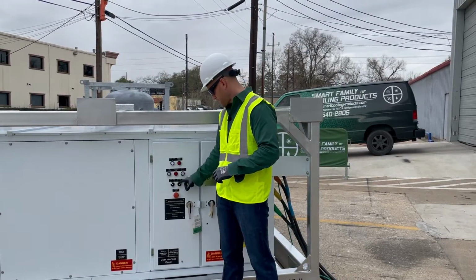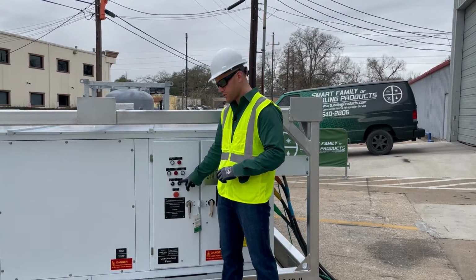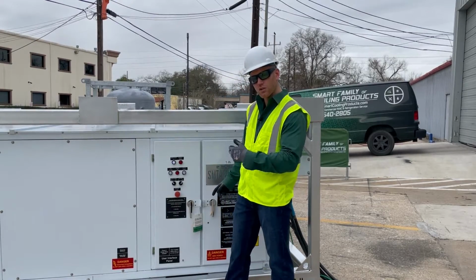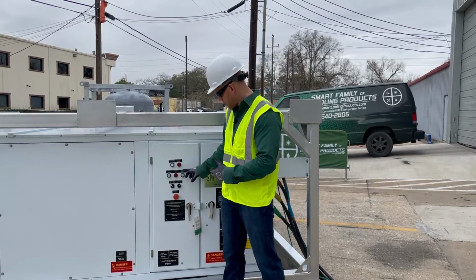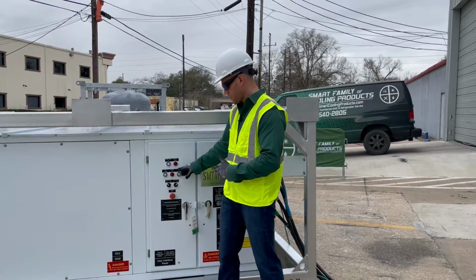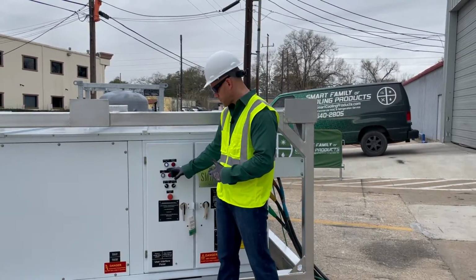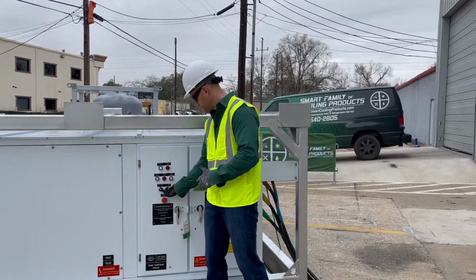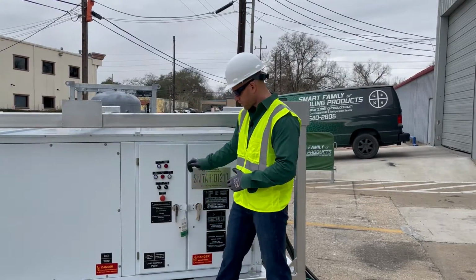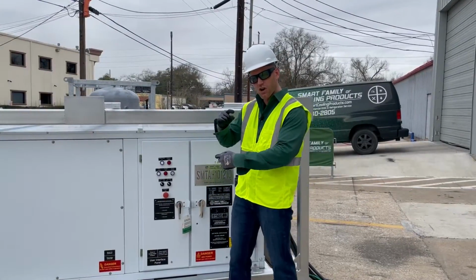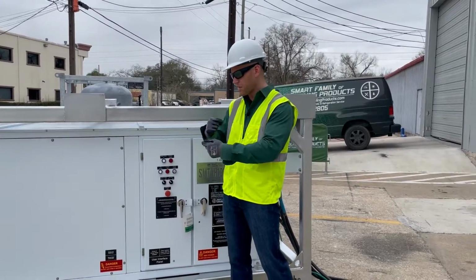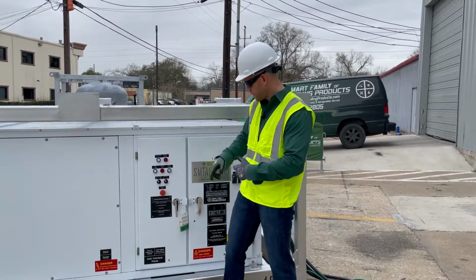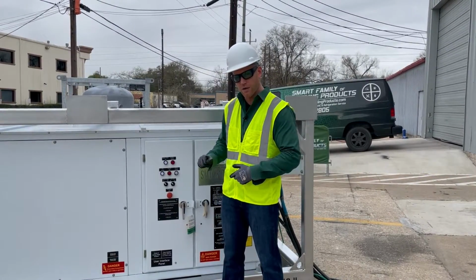And finally, I'm ready to turn the airflow from the off to the on position. When I do this, we should hear the blower starting, and depending upon which switch I'm running, if I'm on VFD mode or bypass mode, that corresponding light will come on. So I turn my airflow switch to the on position. I can already hear that blower starting to spin and start to generate some airflow, and you'll see my VFD light came on.